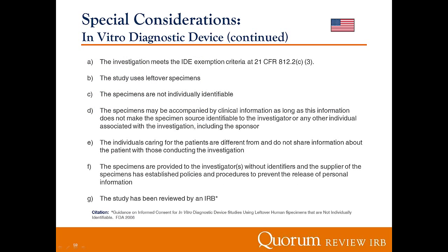So the investigation must meet the IDE exemption criteria, the study must use leftover specimens, the specimens must be not individually identifiable, they must be accompanied by clinical information as long as the information does not make the specimen source identifiable, the individuals caring for the patients are different from and do not share information about the patient, the specimens are provided to the investigators without identifiers, and the study has been reviewed by an IRB. So with in vitro diagnostic devices, understand that indeed you can waive consent, but not in the typical sense. You're waiving consent under the FDA's enforcement discretion.